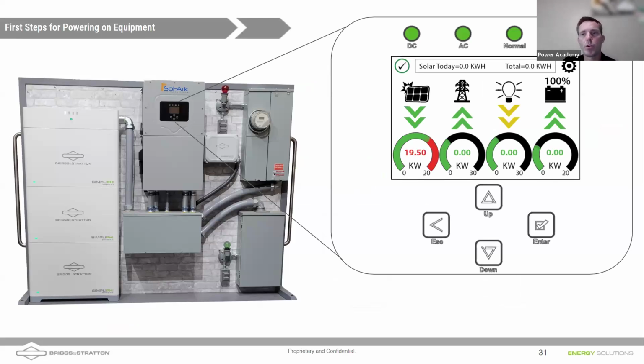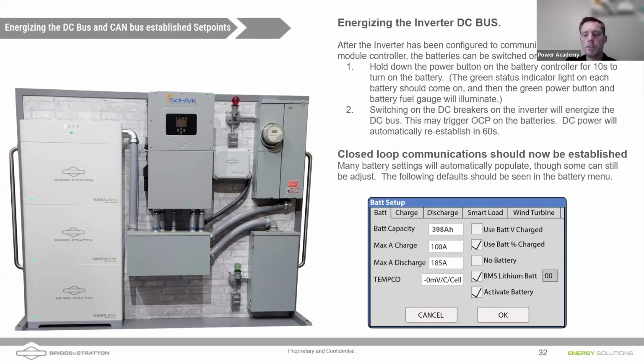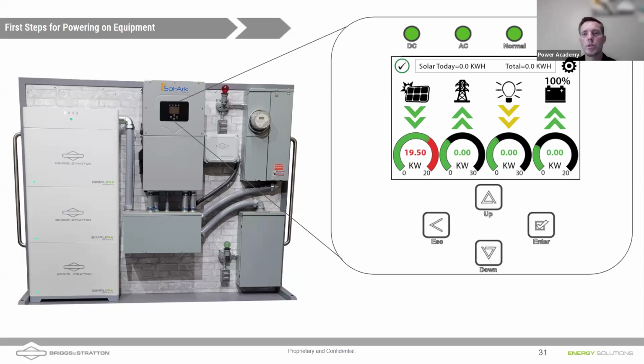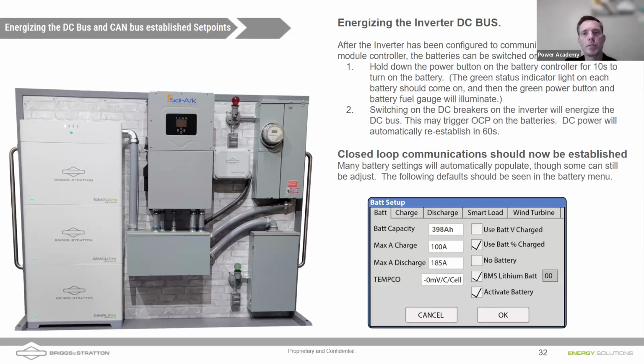To get into the programming, you would hit that gear icon in the top right-hand corner. Once you get into the settings, we're going to go into the battery settings tab. Under that battery settings tab, we're going to go to the BAT tab itself. We want to make sure to check the boxes for BMS lithium battery with the default address of 00 and activate battery tabs, and then click OK to save.